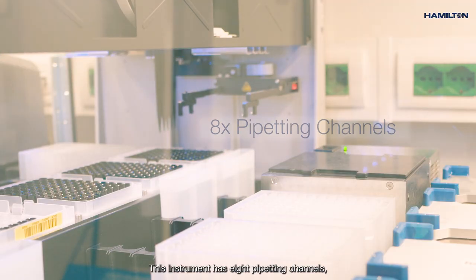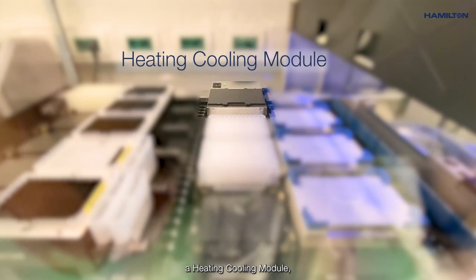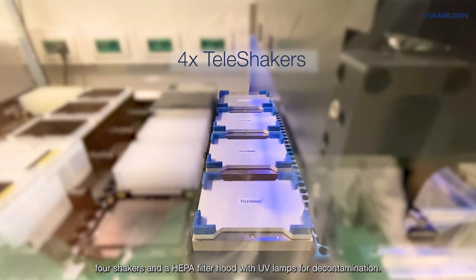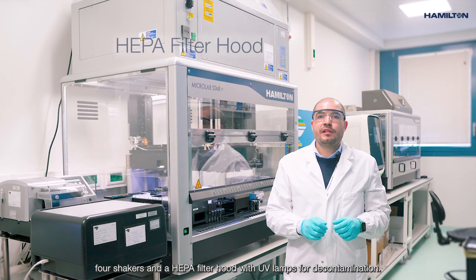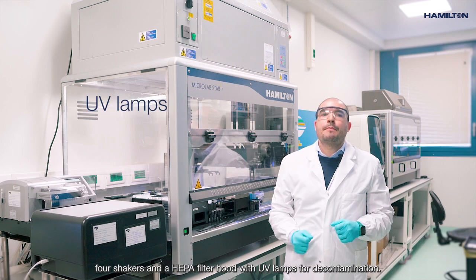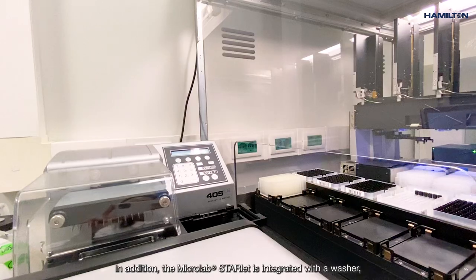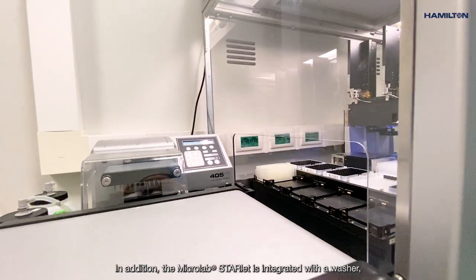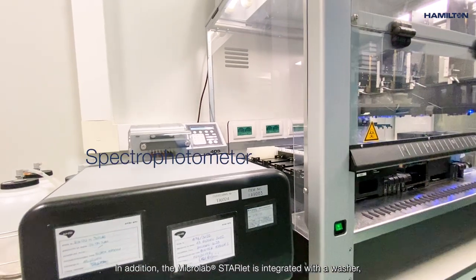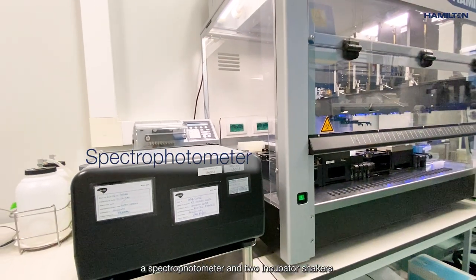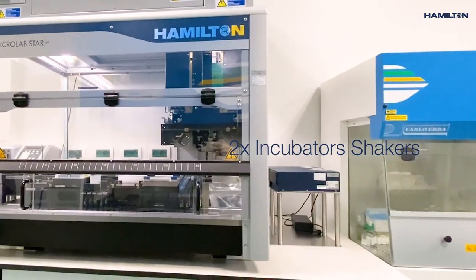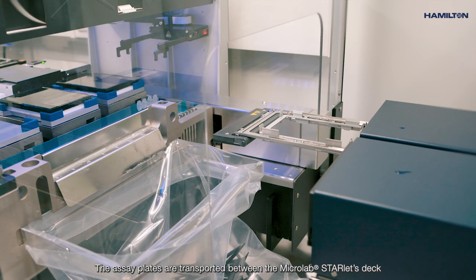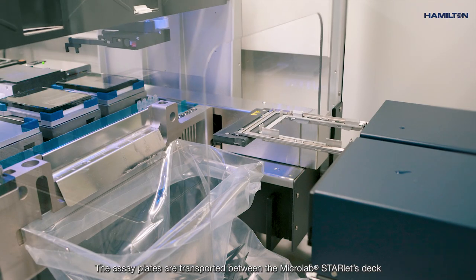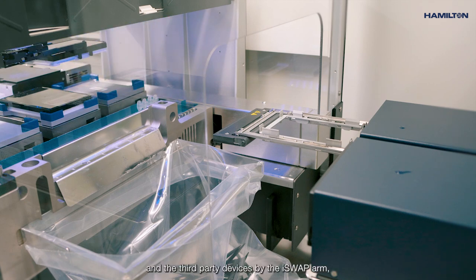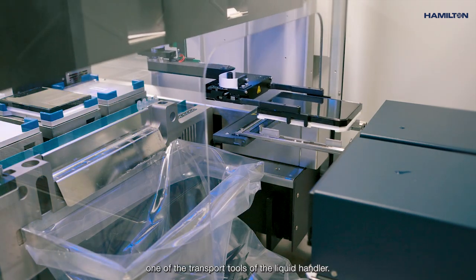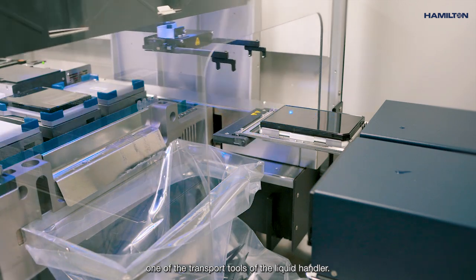This instrument has 8 pipetting channels, a heating-cooling module, 4 shakers, and a HEPA filter hood with UV lamps for decontamination. In addition, the Microlab STARlet is integrated with a washer, a spectrophotometer, and 2 incubator shakers. The assay plates are transported between the Microlab STARlet deck and the third-party devices by the iSWAP arm, one of the transport tools of the liquid handler.